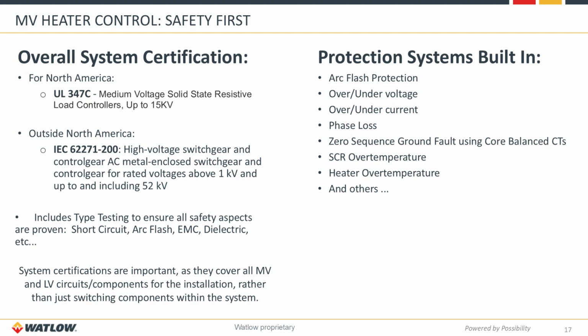In addition to that, we do build in certain protection functions within the system itself. We have arc flash protection, over and under voltage protections, over and under current protections, zero sequence ground faults, SCR over temperatures when you have an SCR within the system, and the aforementioned heater over temperature where we're monitoring those thermocouples and we'll shut down the system if we see any anomalies that are happening. There are several other protection systems built in. Obviously, we have the fusing and the circuit breakers that are part of the overall protection systems, but these are some of the other monitoring type systems we have in the unit to ensure that the system will operate safely.